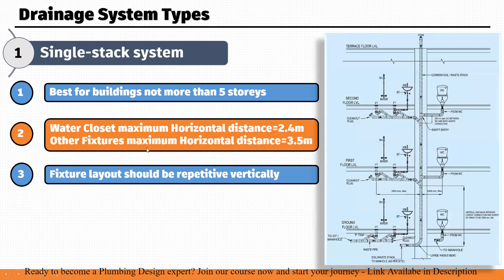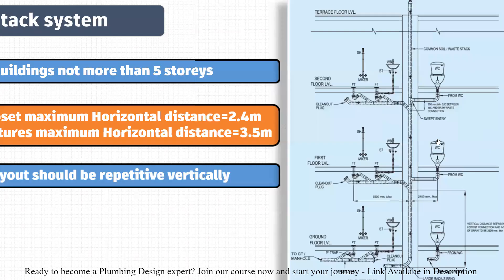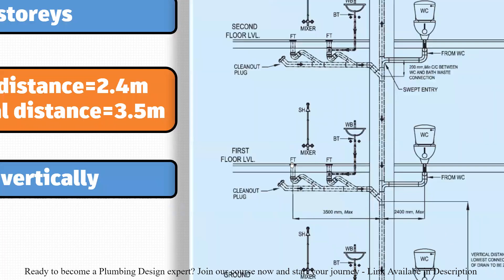The third point is the maximum horizontal distance for other fixtures. For fixtures other than the WC — such as floor traps, showers, and wash basins — the limit is 3.5 meters, or 3,500 mm.